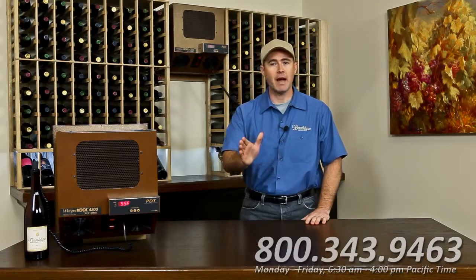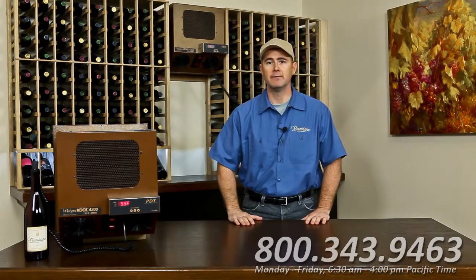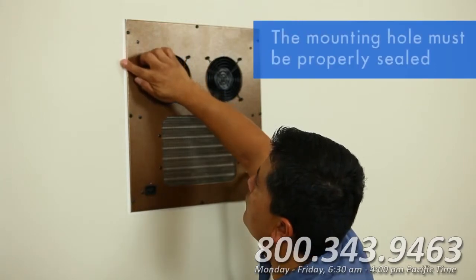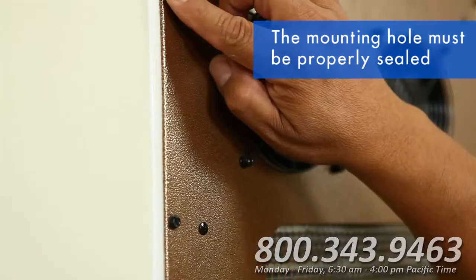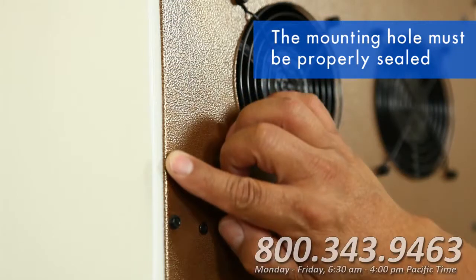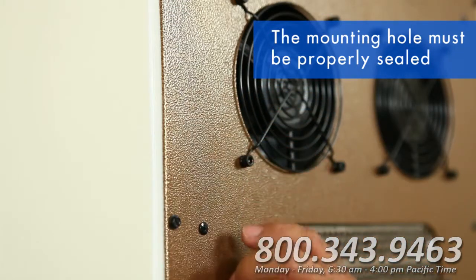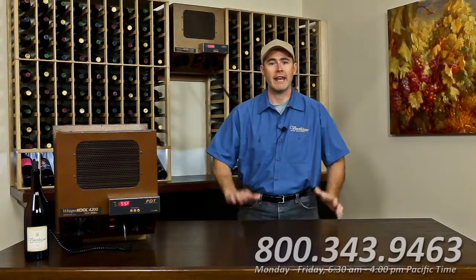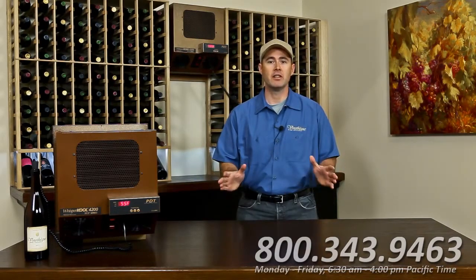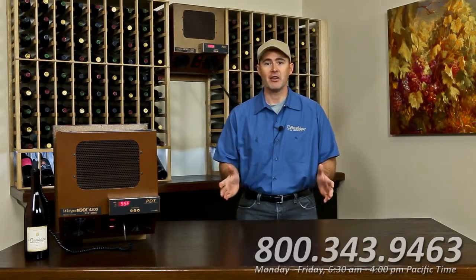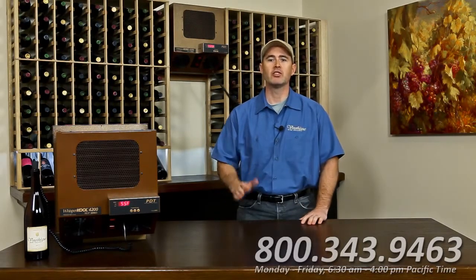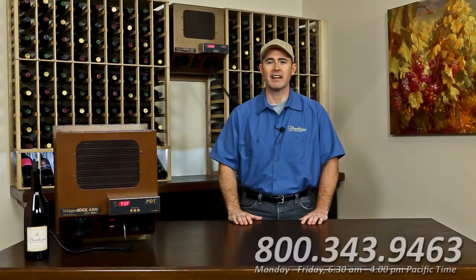Next, check to see if the mounting hole is properly insulated. If you have any warm air flowing back in through the mounting hole, the difference in temperature can cause condensation, which can lead to leaking. Remember that the unit must be level with the ground, and any tilting could cause leaking. You should also check the coils for icing. If there's any ice, it can melt and cause leaking during any time when the unit is not running. If you find ice, now you know the cause of your leaking, but we need to troubleshoot the ice problem. So let's talk about that next.